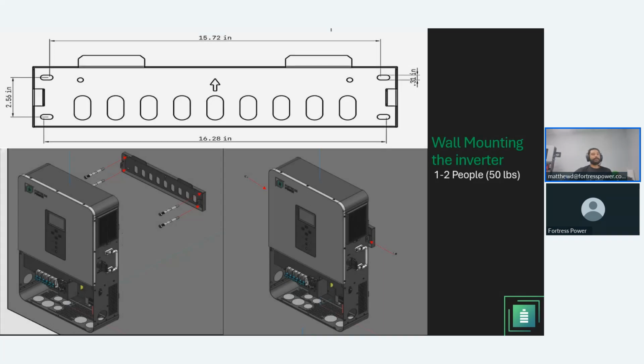All right. First step is going to be, you're going to take the wall mounting bracket, as I mentioned before, 16 inches from side to side. You're going to place it against the wall, and you're going to have a leveler mark the holes of each side, drill the holes, and then fit, whether it's going to be a wood screw or an expansion screw, fit the wall mounting bracket, and then install the inverter on top.